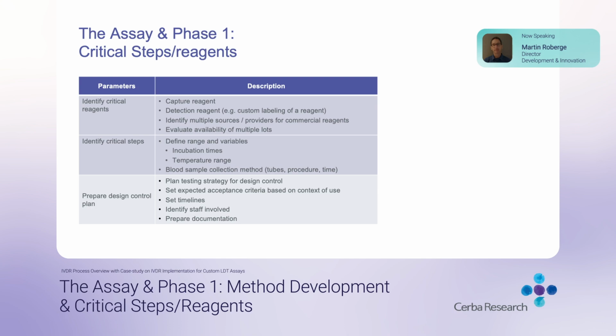So once we have optimized the assay and we have our controls ready, we want to make sure that the assay is going to be fit for method validation. So we recommend running a few experiments that we call pre-validation evaluations, where you're going to be running some validation assessments in the assay. These are very useful to establish acceptance criteria for the upcoming method validation. And it can also be a sign that the assay will need to be re-optimized and brought back to method development if needed.